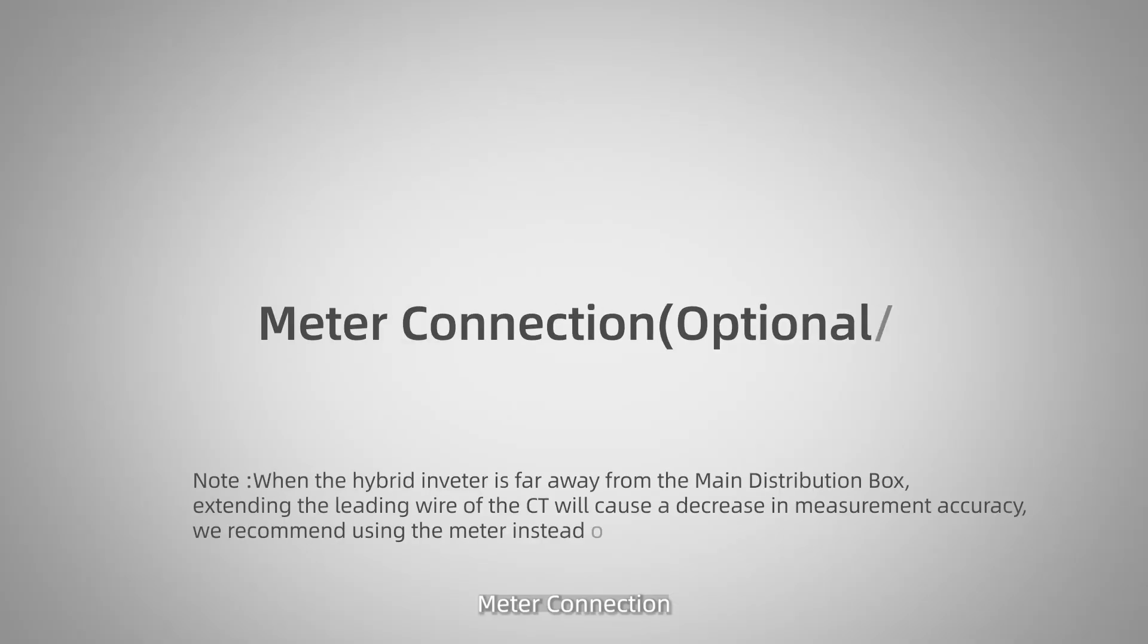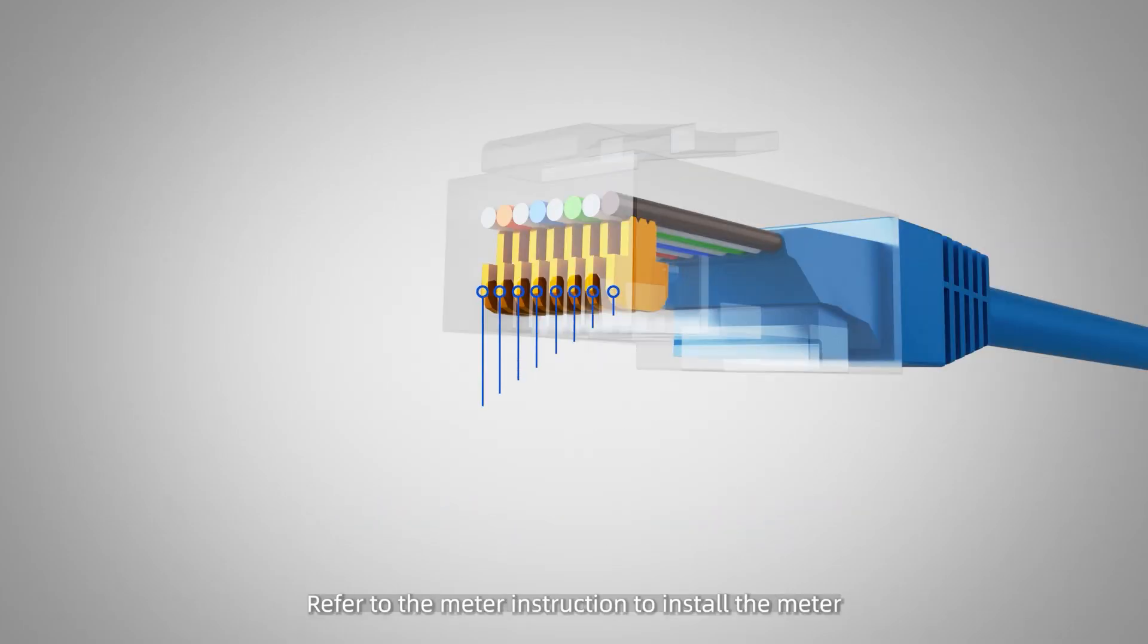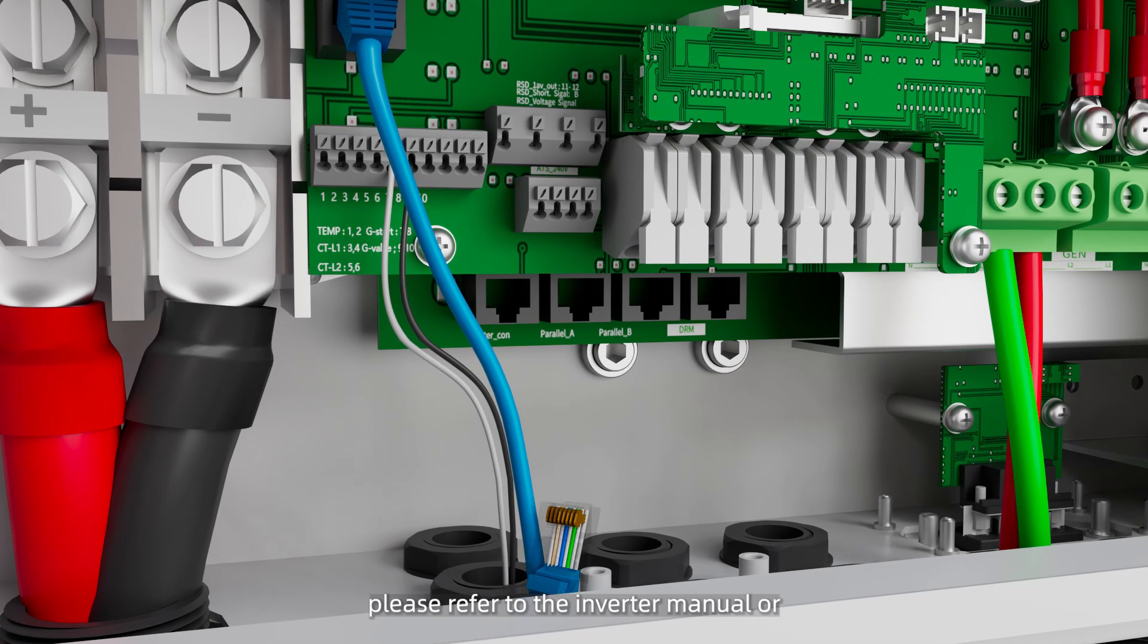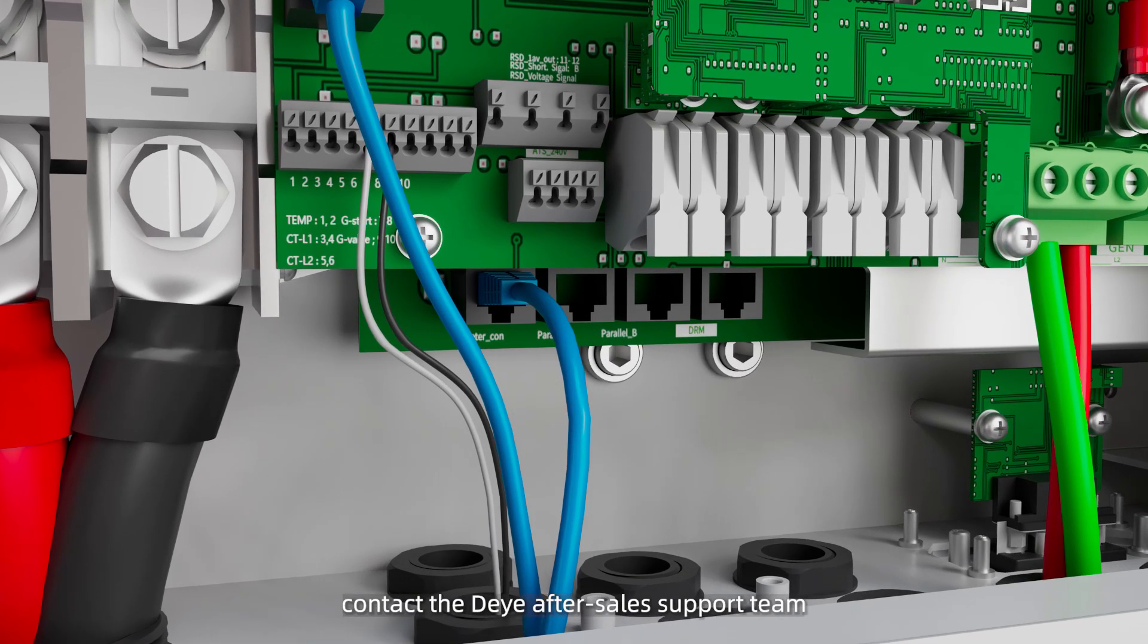Meter connection. In Australia, we usually recommend using the meter SDM120CT. Refer to the meter instruction to install the meter. When connecting the meter CT, the CT always faces towards the inverter. For other types of meters, please refer to the inverter manual or contact the Deye after-sales support team. Connect the RS485 port of the electricity meter to the meter port of the inverter.